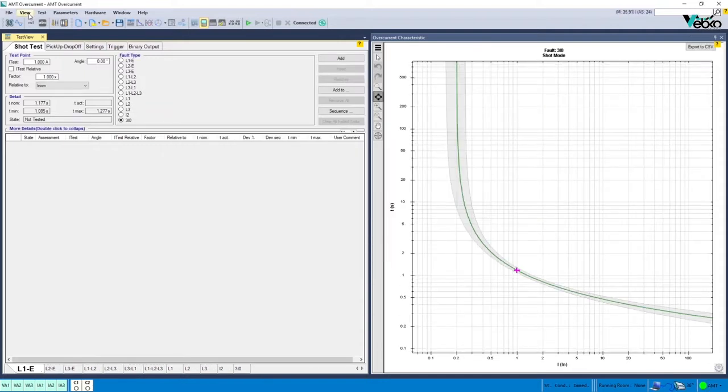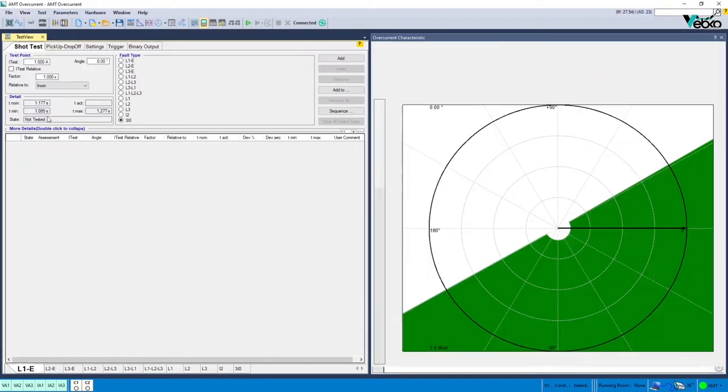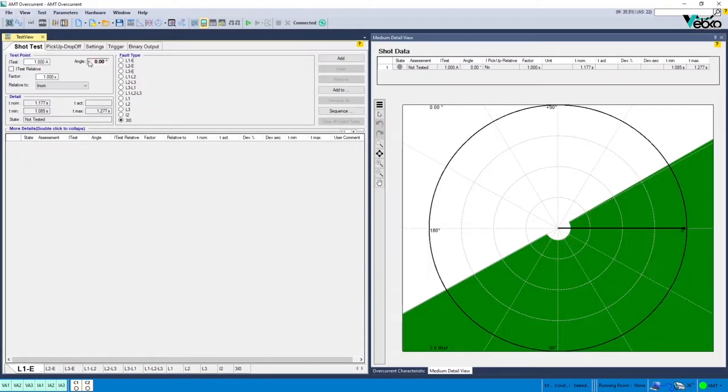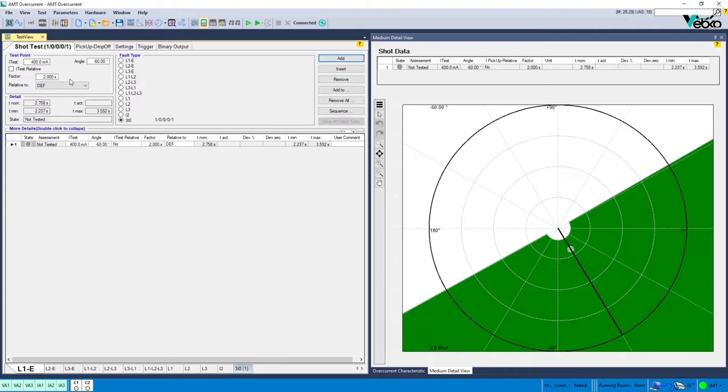In the first step of the test, a current twice the one specified in the setting section is injected into the relay in the best operation angle which is minus 60 degrees. And the operation time is compared to the time predicted by the software.